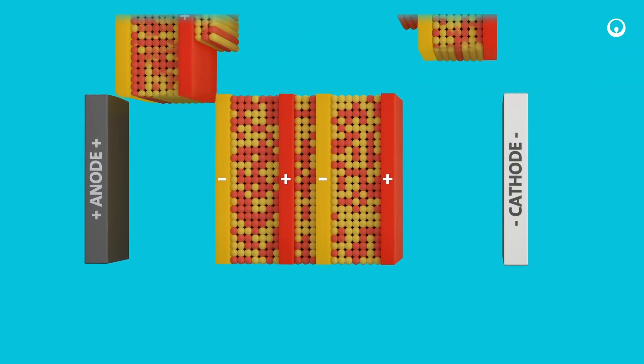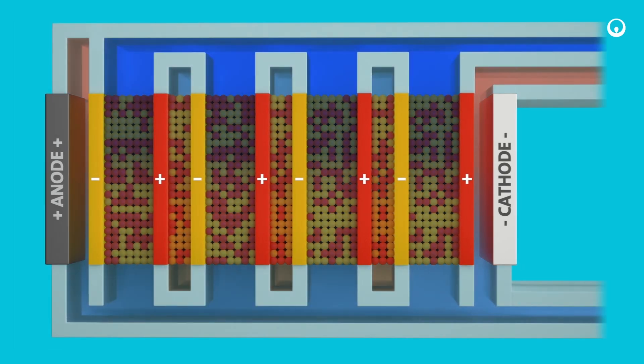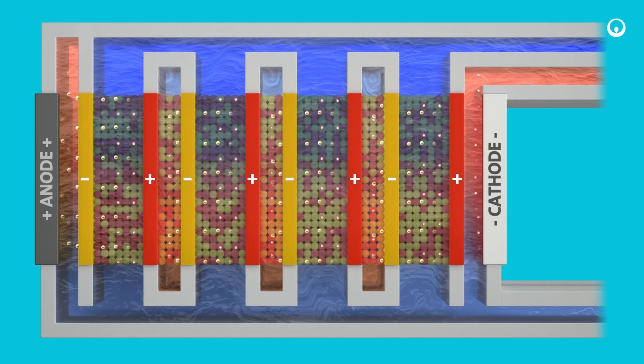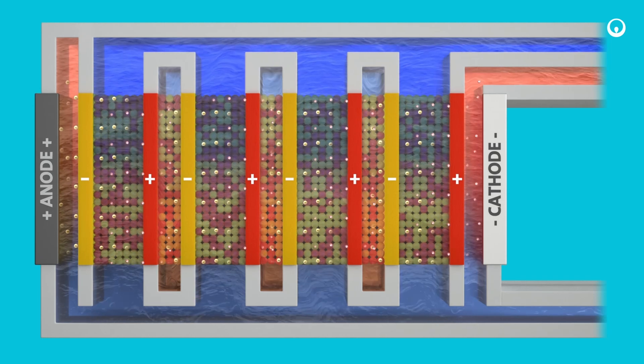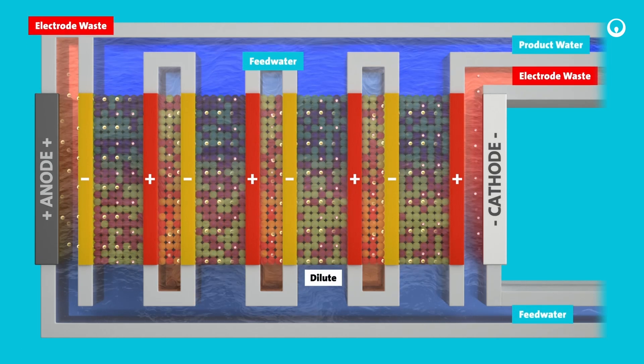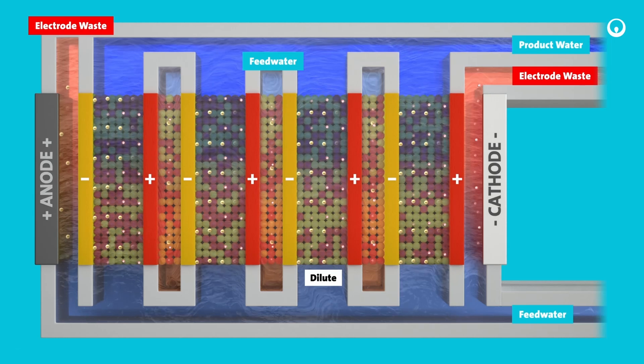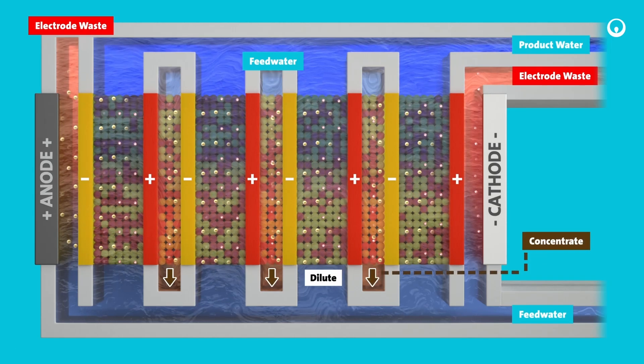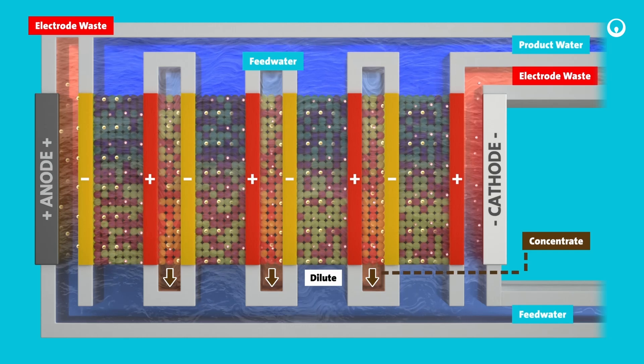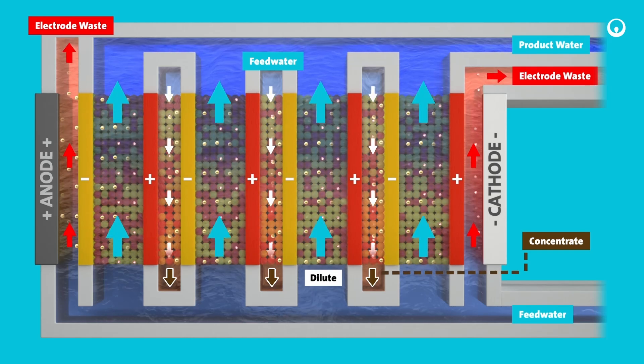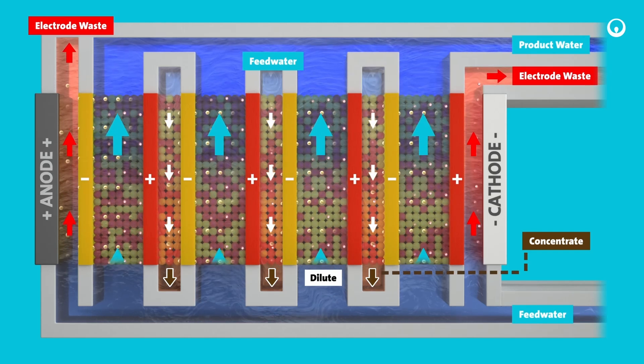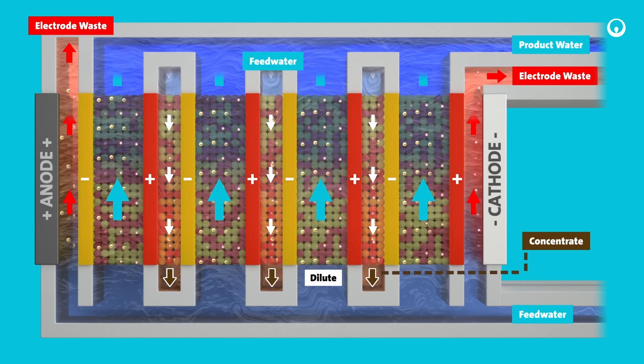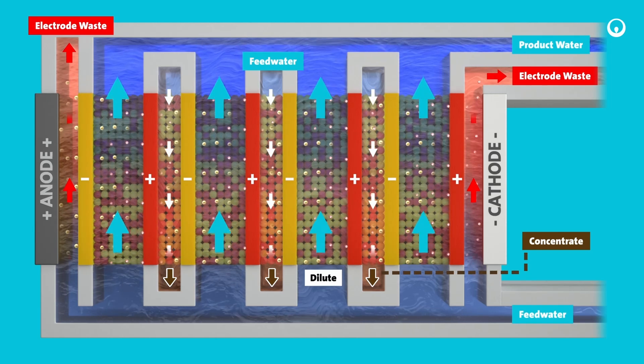Another critical innovative design E-Cell EDI has is the counter-current flow. Counter-current flow reverses the flow through the resin during regeneration. The regeneration flow starts at the opposite end of the resin bed, working first on the least exhausted resin beads, and regenerates the highest concentration of divalent ions last. This regeneration method is two to four times more efficient than the co-current method, dramatically reducing the rate of hardness scaling while keeping performance at a normal high level.